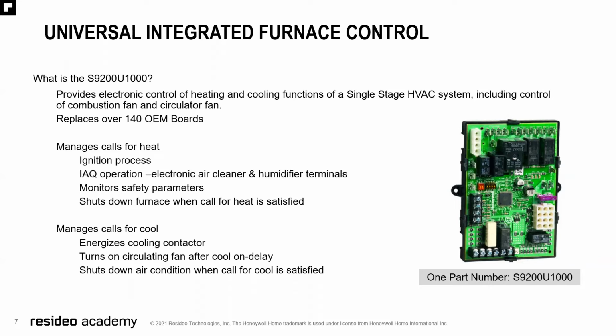It will manage your call for heat, handles the ignition process, has dedicated IAQ operation output terminals for your electronic air cleaner and humidifier terminals. The electronic air cleaner terminals only power up when the fan is on, and the humidifier terminals only power up when the heat is on, when a call for heat has been made. It monitors safety parameters, hooks through your rollout switches and such, high limits. It will shut down your furnace when a call for heat is satisfied.